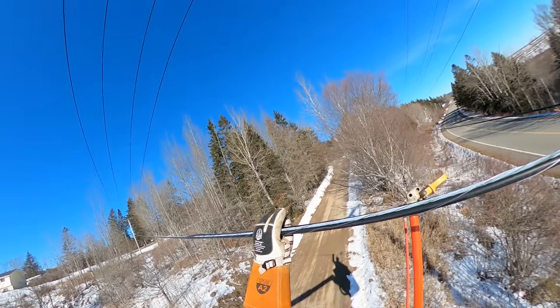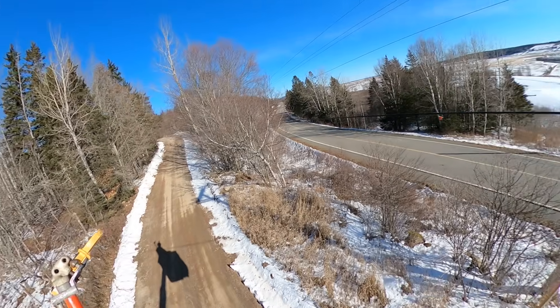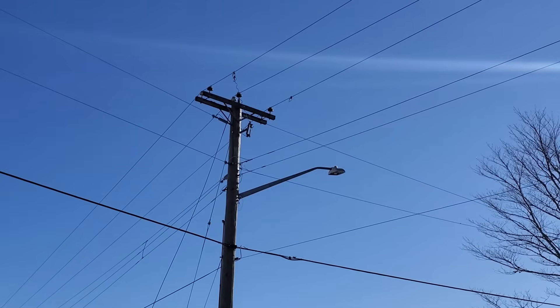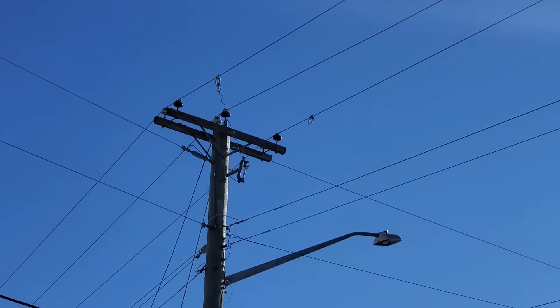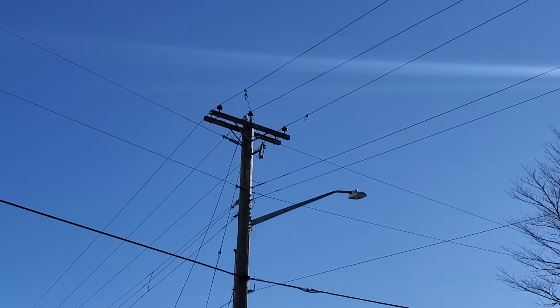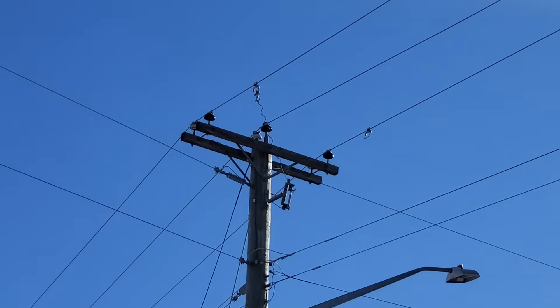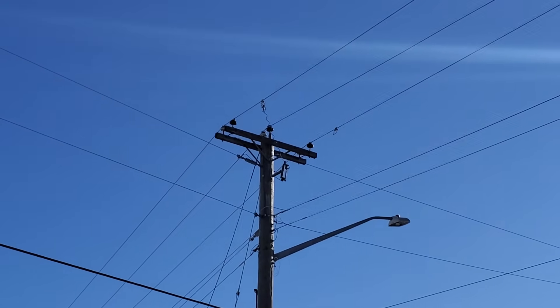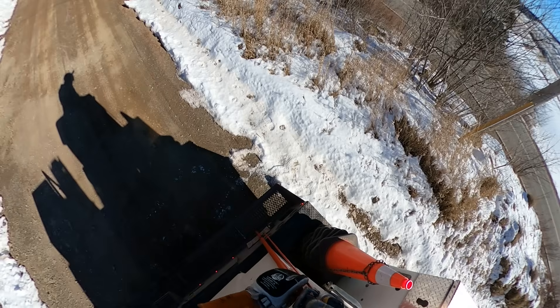That's nothing, not even worth looking at. The other side looks like it's off maybe 20 amps at the most — probably nothing we'll address, but we'll bring it back to the engineers to see if they want to do any load balancing on the lines. This pole is actually a great spot to do some load balancing. Someone left the old stirrup there where a single-phase sideline was fed off the road phase at one point — now it's on the field phase. You can't parallel two different phases while energized, so we'd have to open the cutout, grab that tap clamp, swing it over into the road phase, and that'll put more load on A phase to balance things out. There's probably about 25 houses on this sideline.